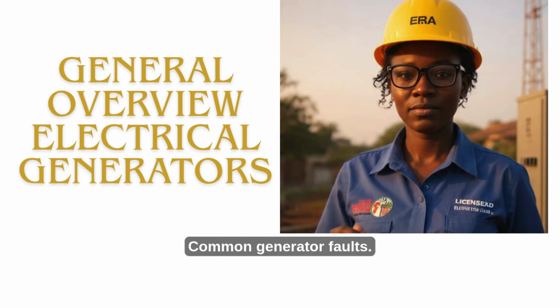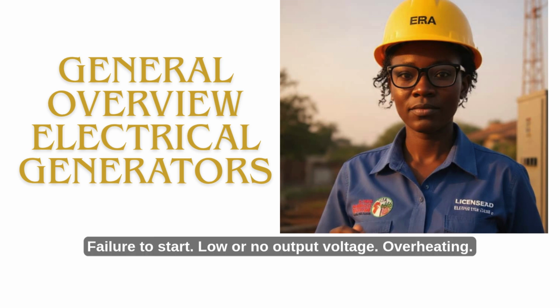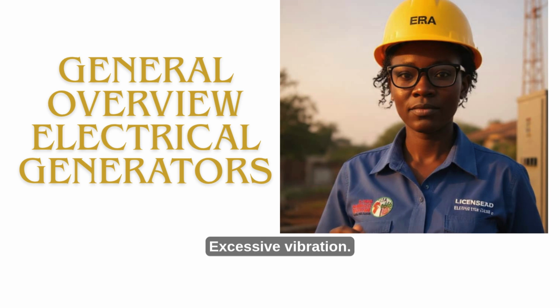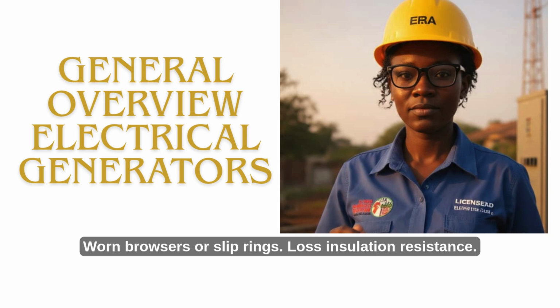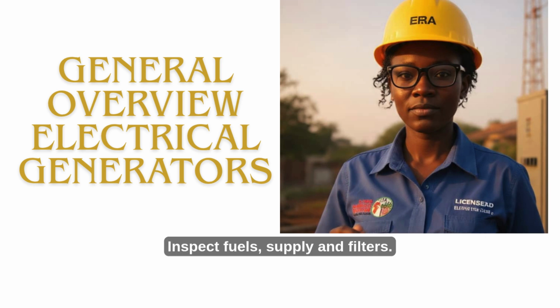Common generator faults: failure to start, low or no output voltage, overheating, excessive vibration, worn brushes or slip rings, low insulation resistance, bearing failure, fuel system problems, overloading. Maintenance practices: check engine oil or coolant levels, inspect fuel supply and filters. Clean air filters regularly.